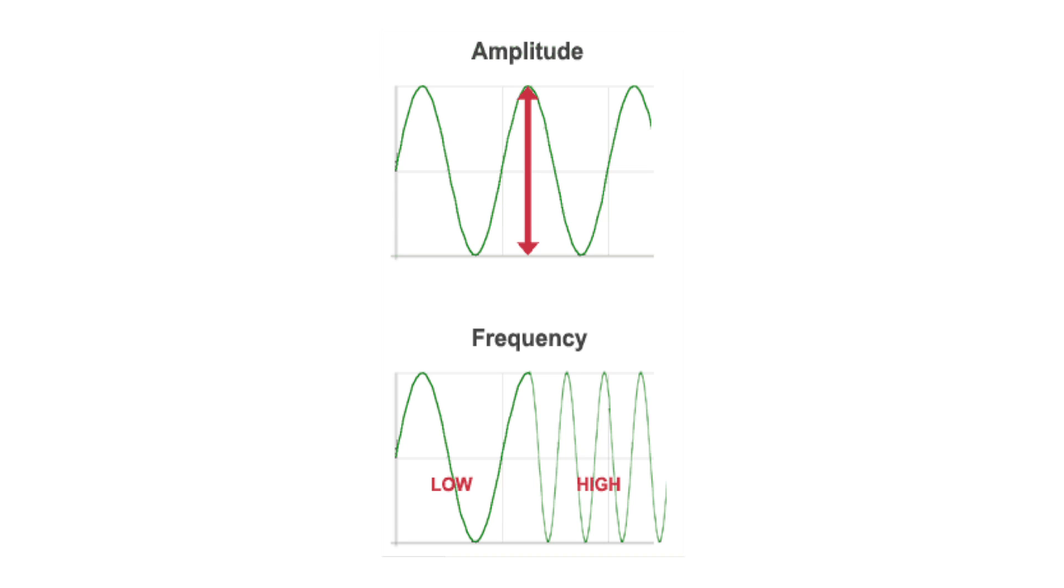That is, greater than 20,000 hertz. The A-scan probe emits sound at a frequency of 8 or 10 megahertz, 8 or 10 million hertz.